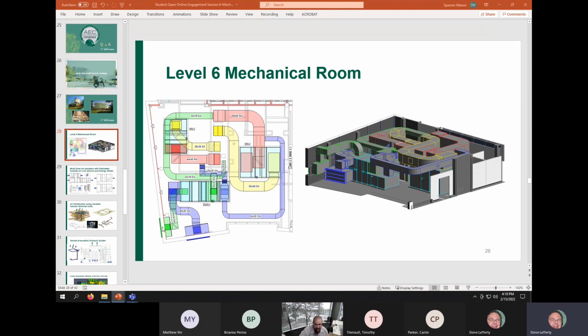So the outside air is delivered to the unit itself, air handler 1 and air handler 2, through the return duct, which is in red. And then the unit with the yellow ducts there blows all that air down through a shaft and delivers it out to the different floors. So this is not a single zone unit like we were discussing previously at the other center of the football field. This is a multi-zone unit. So there's quite a few zones. If I remember right, it's over 100 different zones that we have attached to these 2 units that are being fed outside air through that DOAS unit sitting right there.